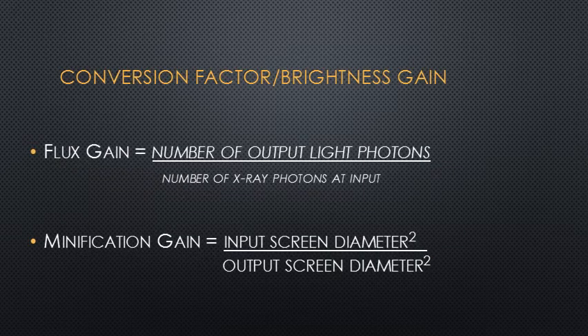Remembering from prior discussion, brightness gain references factors of flux and minification. Flux is the ratio of the number of output light photons over the number of input x-ray photons — or, said more simply, using a few x-ray photons to produce many more light photons. This is the image intensifier's conversion efficiency.